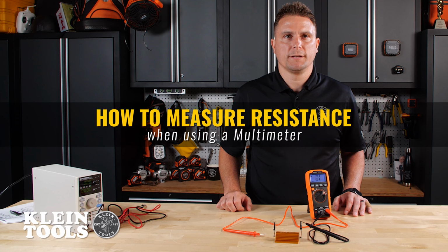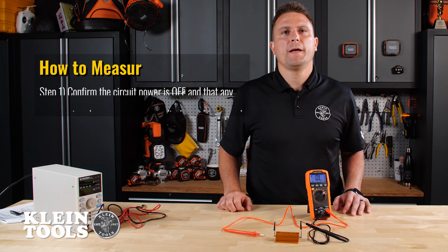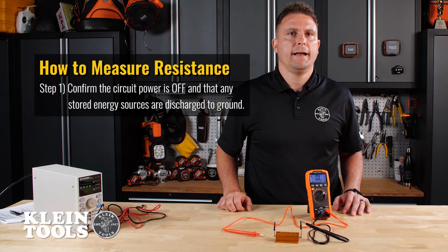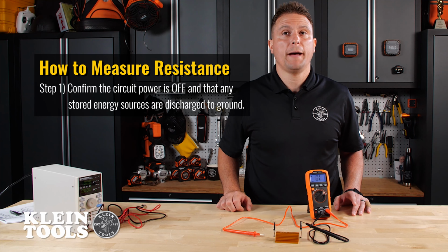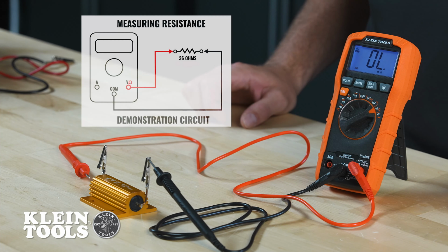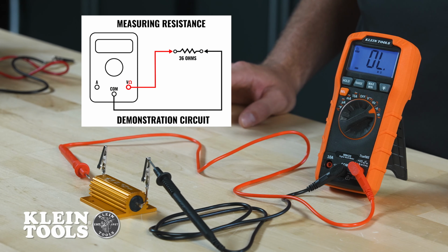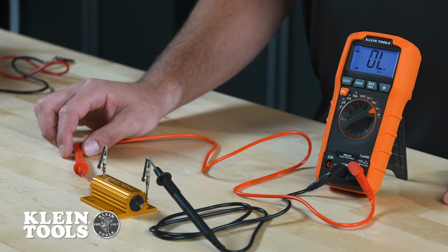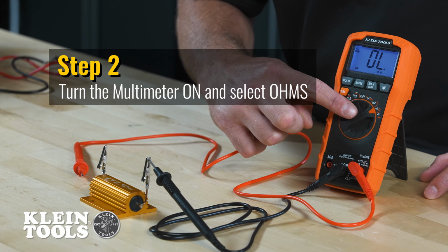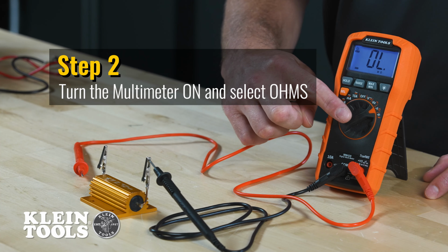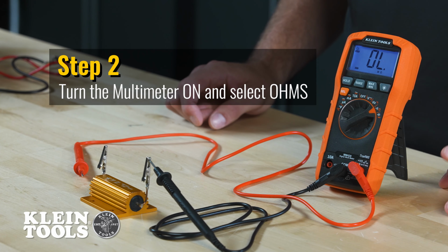Here's how to measure resistance. First, confirm that the circuit power is off and that any stored energy sources, such as capacitors, have been discharged to ground. We don't have an energy source connected in this particular demonstration, so we can skip that step. Turn the multimeter on and select it to ohms, which we've done here already. The display should read infinity ohms, OL, on the display.